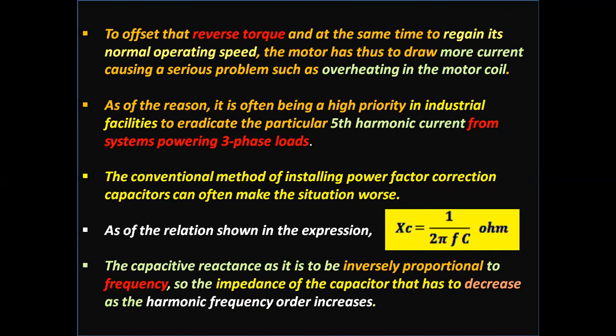The conventional method of installing power factor correction capacitors can often make the situation further worse. From the expression XC = 1/(2πfC) ohms, the capacitive reactance is inversely proportional to frequency, so the impedance of the capacitor decreases as the harmonic frequency order increases.